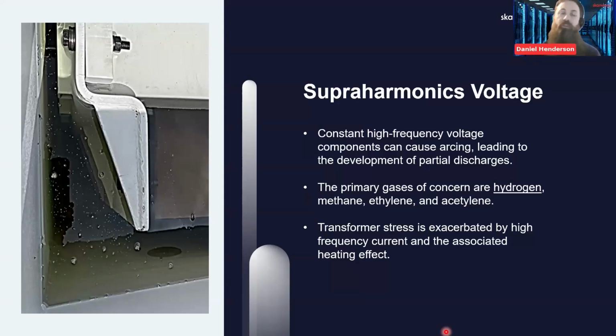Yeah, it's really interesting actually, because in other industries and other fields, typically when we're doing our oil analysis, you do your DGA analysis, but you don't often see, from what I've seen especially in the PV or the solar industry, a high amount of gassing in the transformer, so high amounts of DGA. And I've seen it where it's just an accepted thing, because obviously you've got these micro arcs and PD because of the nature of the inverters and then the impact on the network. But it's something that you would never accept in other parts of industry, in standard distribution or any other manufacturing, as an example. The types of loads, you wouldn't tend to see this.